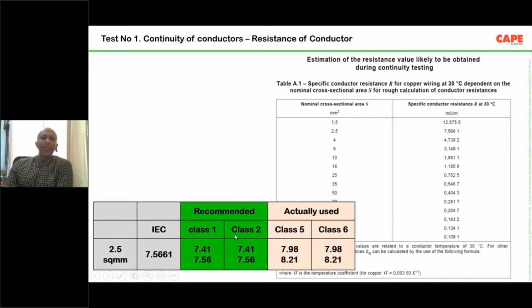There are two kinds of conductors available in India. They're not two, actually, four kinds of conductors. Conductor means the copper inside a wire. There are four types of copper used inside a copper wire. Class 1 means a solid conductor. Class 2 means a multi-strand conductor. And the resistance I have mentioned here, 7.41 and 7.56. 7.41 is bare copper conductor, and 7.56 is the resistance of the conductor with a tin coating. So class 2, 7.41 and 7.56.